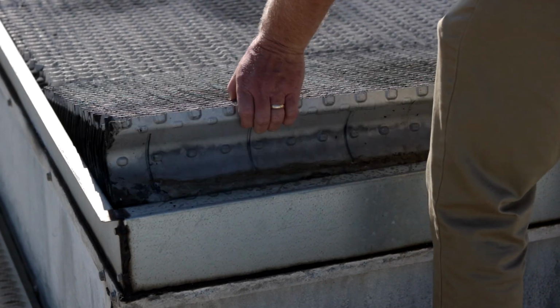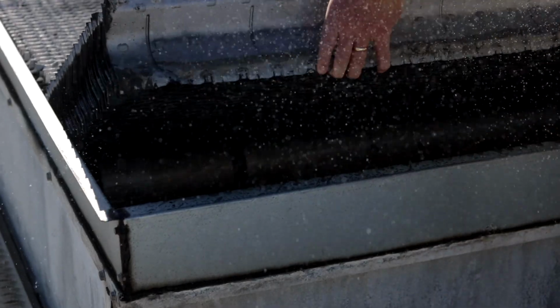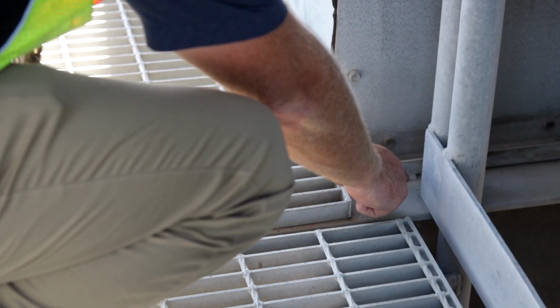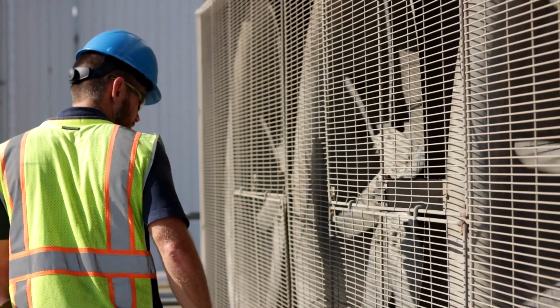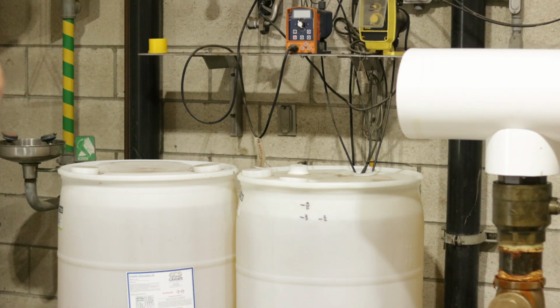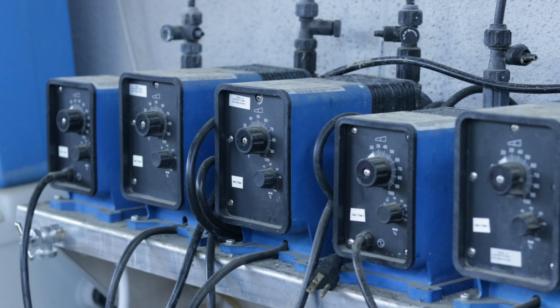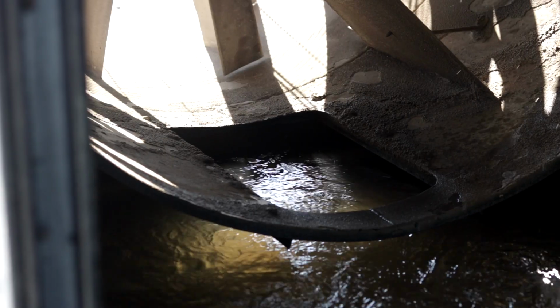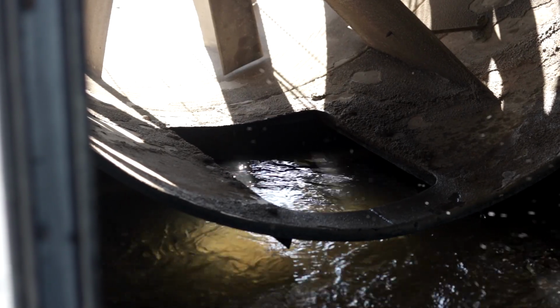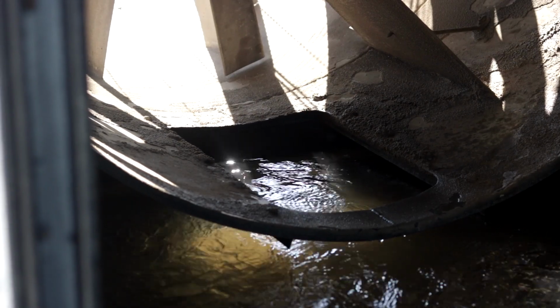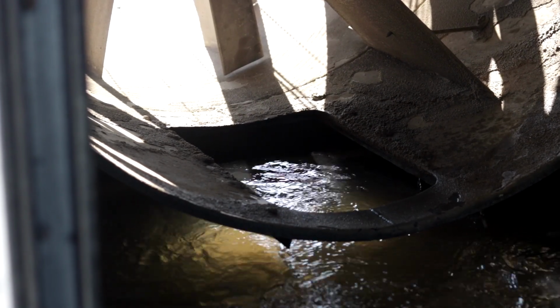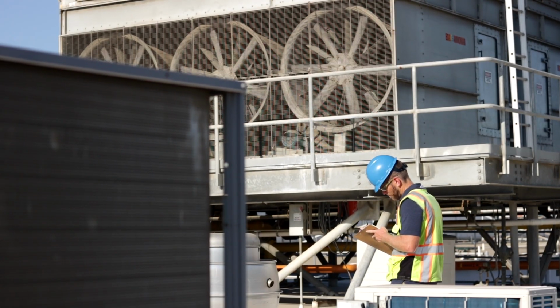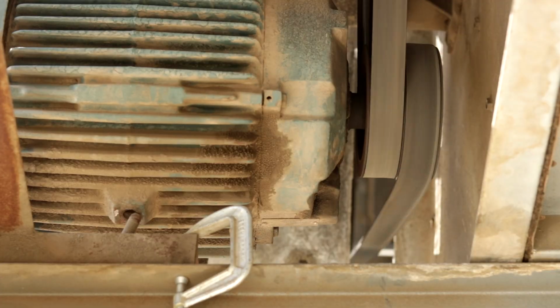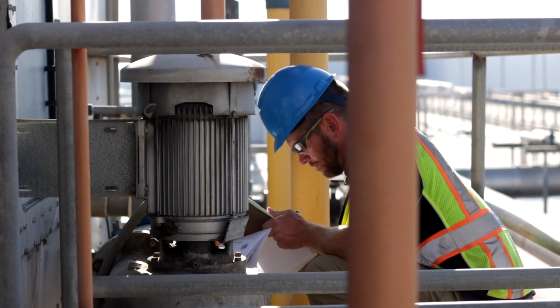Annually, the inspection should be more thorough and verify the water distribution system is working, anchorage is adequate, fans, shrouds, and hubs are in good condition. The water treatment system for evaporative condensers must be tested at least monthly to ensure it is within tolerable limits. The water sump on an evaporative condenser will require periodic cleaning based on the location and duty of the condenser. Other maintenance tasks that the operator must be aware of include replacing fan belts and lubricating fan and pump motors.